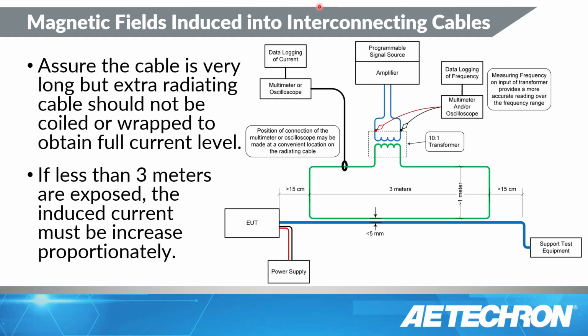The other thing is I tend to make these cables very, very long, 7, 8, 9 meters, 10 meters long. The reason why is that I don't know where I'm going to be able to expose 3 meters. It may be some remote place, plus the fact you have to find your way all the way back to the transformer. Well, I've already got 6 meters plus this distance, so that's a meter here, meter there. That's 8 meters of cable that I require just to perform this. So 9, 10 meters of cable may be what you're going to have.